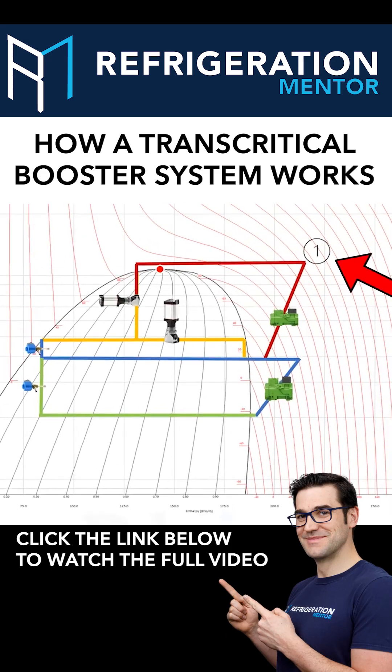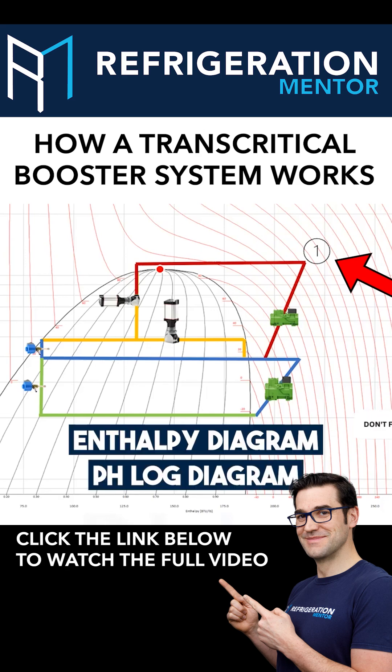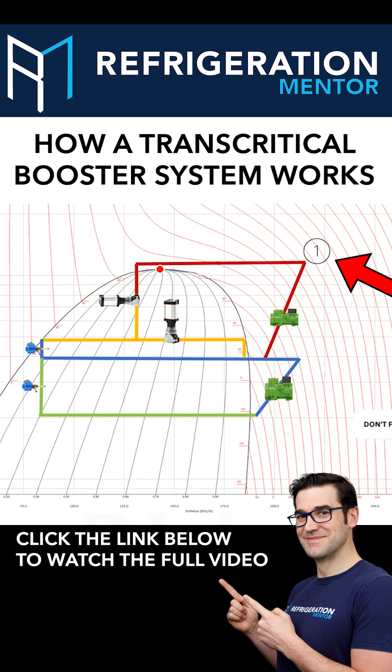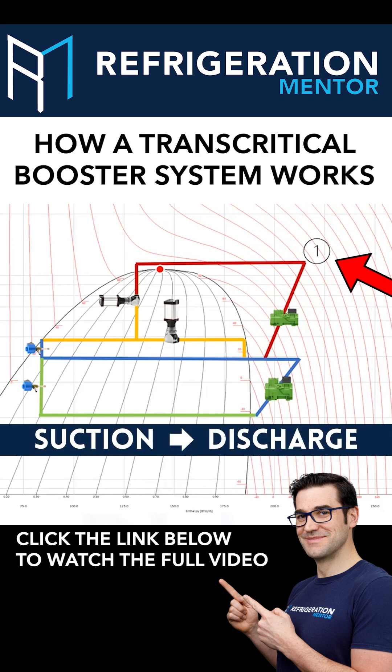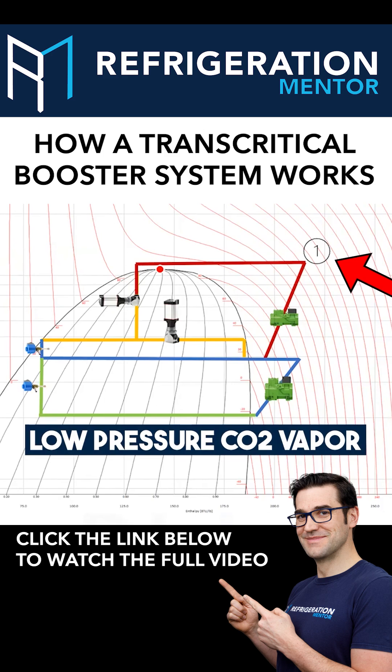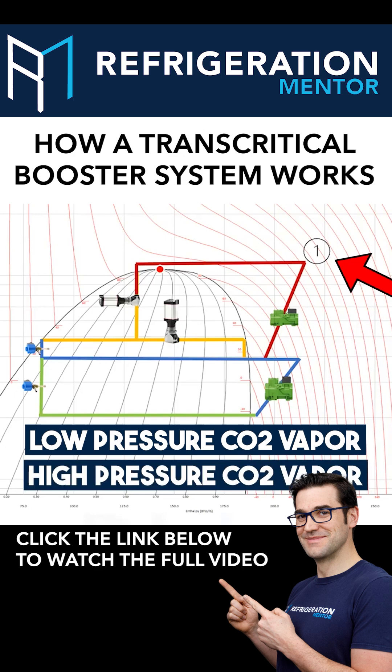If you're looking at the screen, we get this point one. So if you think about the enthalpy diagram or the P-h log diagram, and I'm going to call it the log diagram going forward, the first step is going from your suction to your discharge. So you have that low pressure CO2 vapor going into a high pressure CO2 vapor.